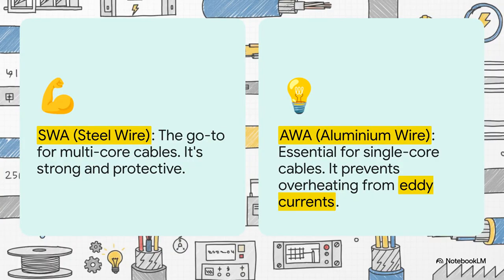Okay, so this is the really crucial part, the big difference between steel and aluminum. For cables that have multiple cores inside, strong protective steel wire armor, SWA, is the go-to. It's a beast. But you absolutely cannot use it on a single core cable. Why? Well, it's all about physics. The alternating current flowing through that one conductor would create a magnetic field in the steel armor. These are called eddy currents, and those currents would cause the cable to heat up, like a lot, and eventually fail. Aluminum, because it's non-magnetic, completely sidesteps this problem. It's a perfect example of how the laws of physics directly shape engineering choices.